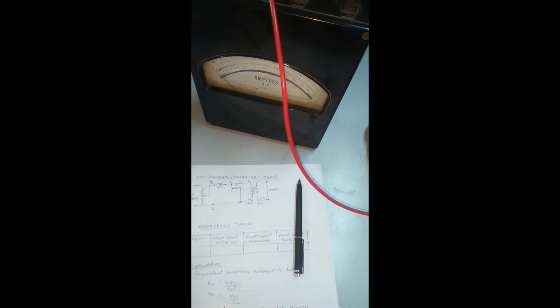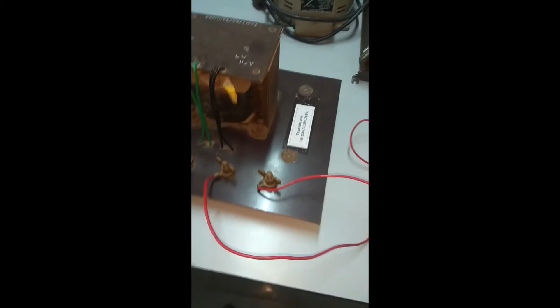Now the remaining connection is that we need to short M and C in the wattmeter. So here we have shorted M and C using this connecting wire. Then in the transformer we need to short the LV, so LV will be shorted here. So we have used one wire for shorting this LV, so it is shorted, you can see it, this is shorted, LV is shorted.